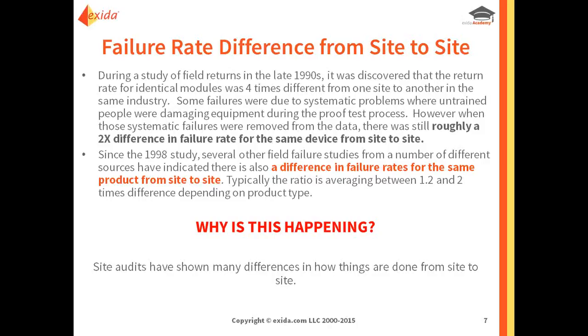During a study of field returns in the late 1990s, it was discovered that the return rate for identical modules was 4 times different from one site to another in the same industry. Some failures were obviously due to systematic problems, where untrained people were damaging equipment during the proof test process. However, when those systematic failures were removed from the data, we still saw roughly a 2 times difference in failure rate for the same device from site to site.